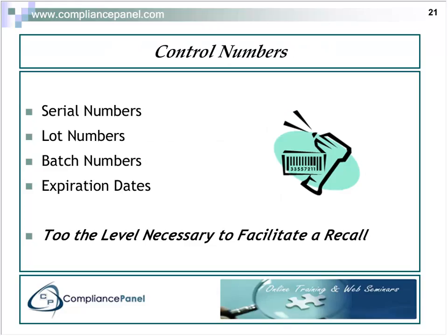And then we get to control numbers. What were the serial numbers that were included in this release, in this particular device history record? Lot numbers, batch numbers, expiration dates. And again, I stress to the level necessary to facilitate a recall.